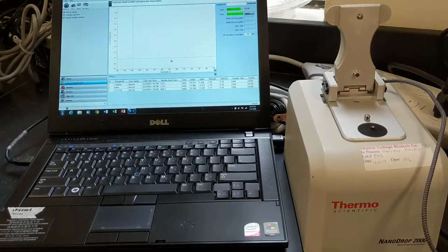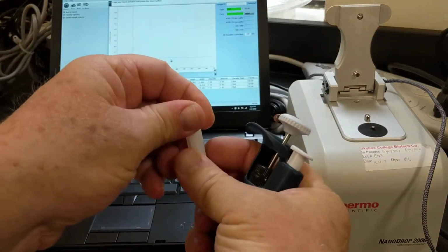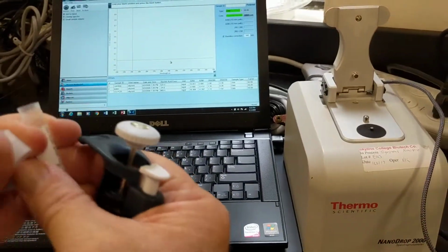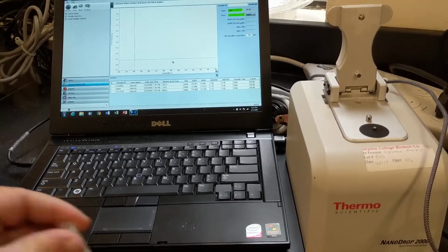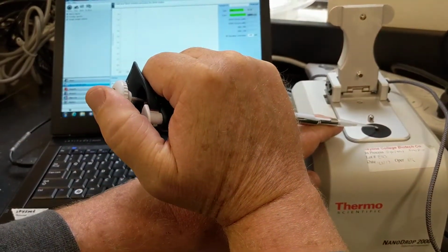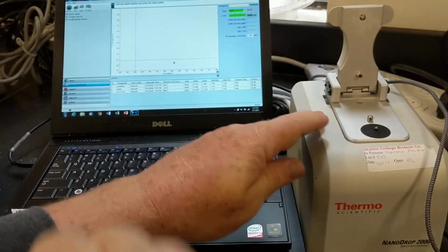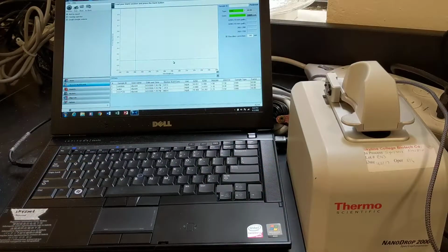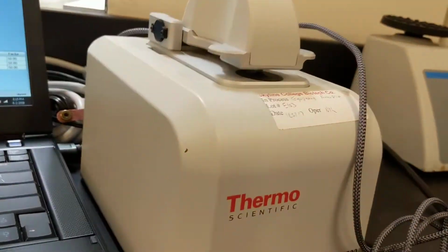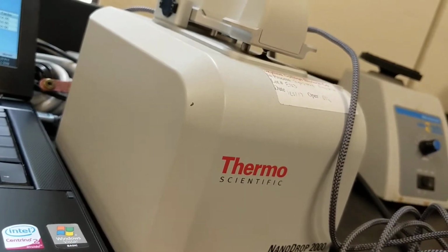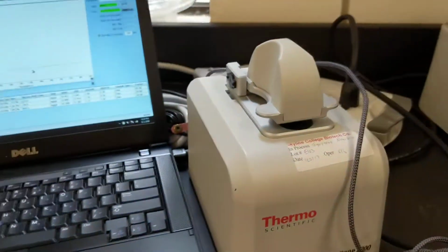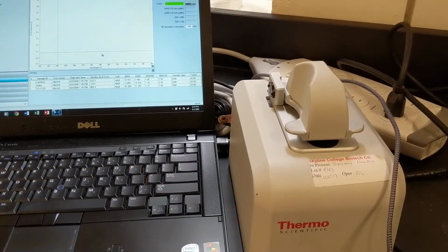The first thing that we want to do is blank our piece of equipment. So what I'm going to do is grab a pipette, go in and grab out 2 microliters. Sorry about the bouncing. And then I'm going to put the 2 microliters on the very end of the pedestal. If I close the pedestal, again, you need to look and make sure that there is a connection. If you look on there, you should be able to see the connection that's in there. All right.